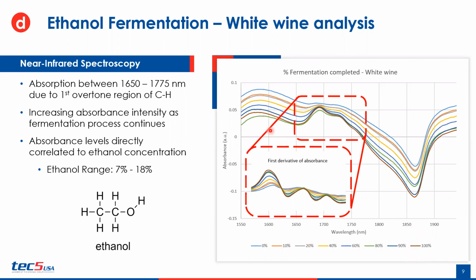Looking at the spectra itself, we're observing the absorbance spectra of the white wine sample in the near IR spectral range. Looking at this inset here in red, this is the absorption between 1650 and 1775 nanometers, and this is due to the first overtone region of the CH groups in ethanol. Looking at this region, you can take a quick snapshot and look at a first derivative of this absorbance spectra. What the first derivative does is allow you to look at the trends in the data and, ultimately, correct for any baseline levels.